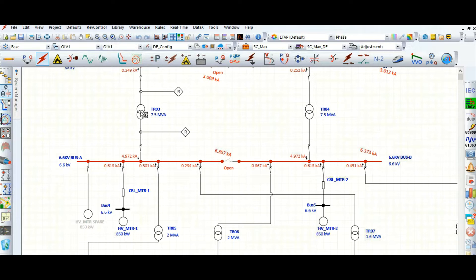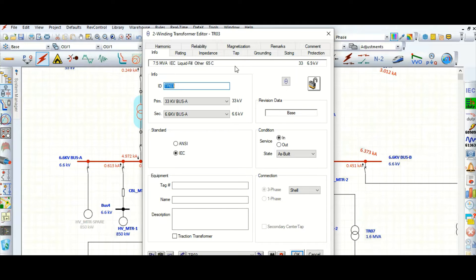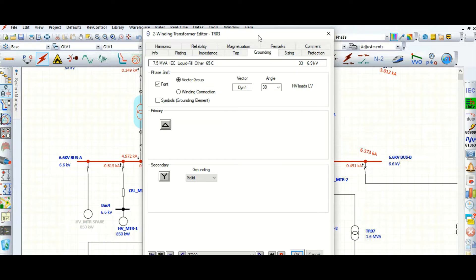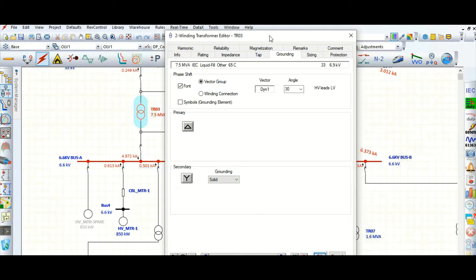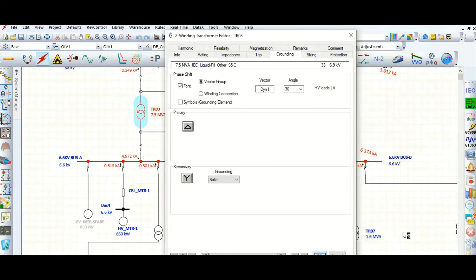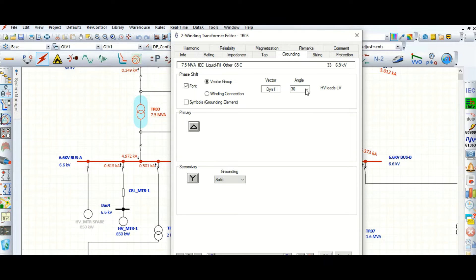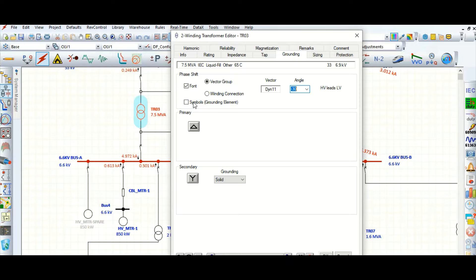Let's go to the transformer grounding tab. This is a 7.5 MVA transformer and the secondary side is 6.6 kV. The grounding symbol shows delta-dyn, so let's change the vector group to Dyn11 by setting it to minus 30 degrees.